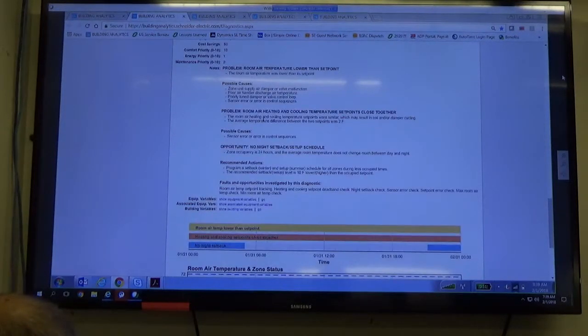The other point on this diagnostic is that the room air heating and cooling temperature set points are close together. The average temperature difference between the two set points is 2 degrees. I've noticed this on just about all the VAV boxes. Building Analytics recommends at least a 3-degree difference. That's something we can discuss more later, it's more of a technical question. We can always change that threshold, but Building Analytics is telling you that if possible, 3 degrees is the difference you'd like to have.